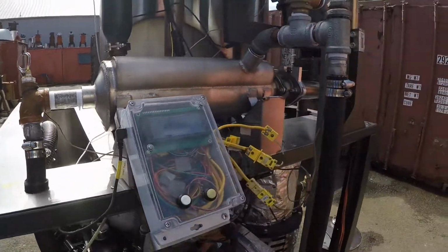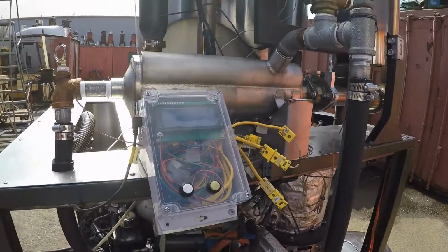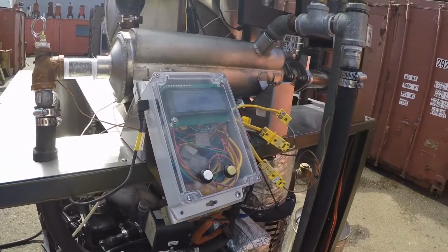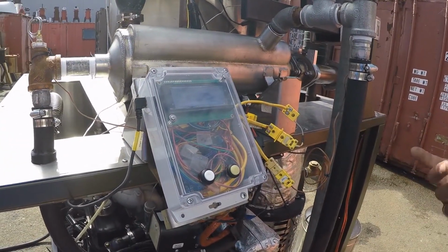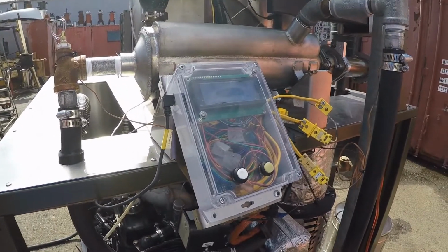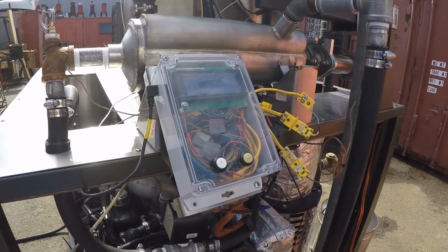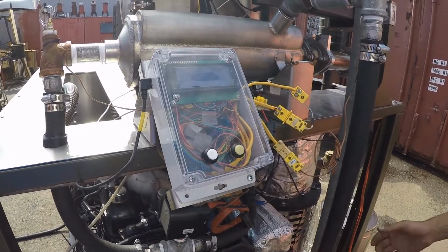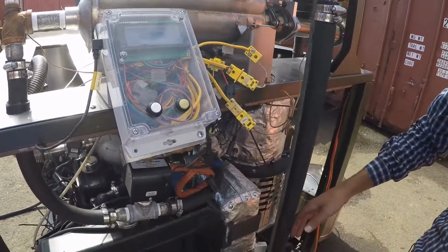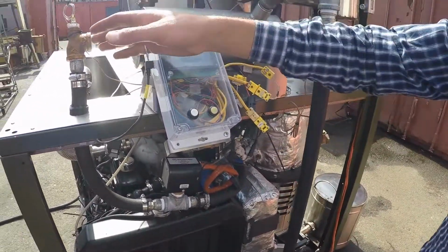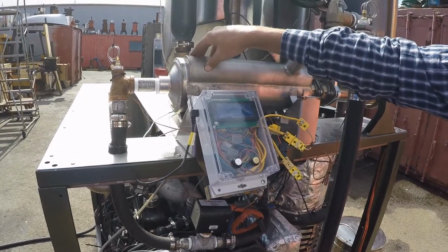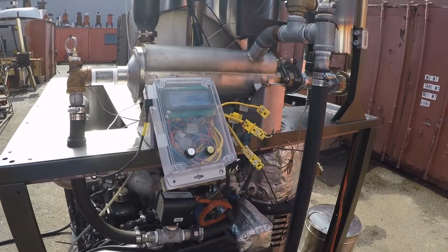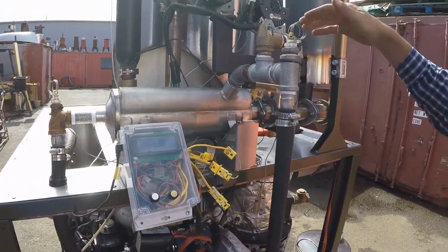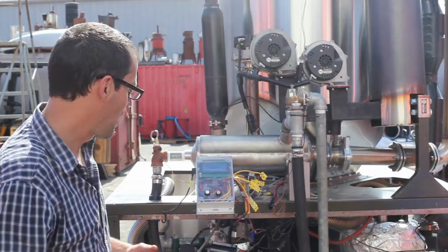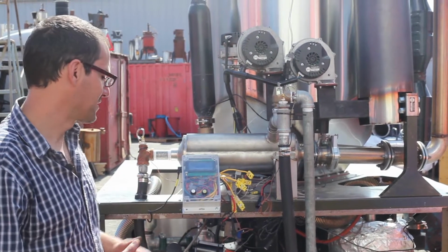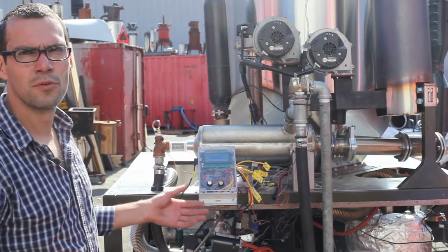Our monitoring system here is our first alpha unit. Just an Arduino board with 5 thermocouples. We're measuring the water temperature into the plate heat exchanger. We measure the water right before it goes into the shell and tube heat exchanger, and then we measure the water temperature coming out of the shell and tube heat exchanger. And we're also measuring the exhaust gas temperature and the engine coolant water temperature.